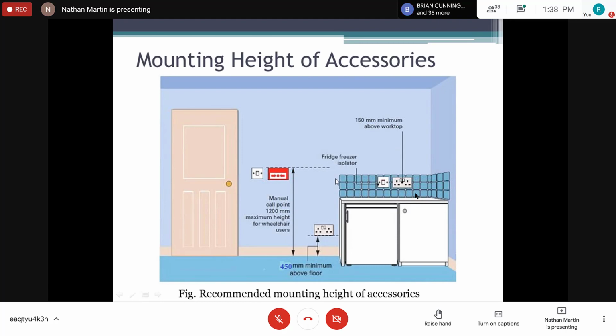All right, so this is basically just typical mounting heights. However, we're talking about from the finished floor. So if you are doing a new installation, guys, you need to make allowance for your tiles. But what if they never put in the flooring before and you need to position your boxes? The diagram will indicate the measurement from the finished floor to the ceiling. This is why the diagram is an elevation plan. It will show you what this distance should be, whether it be 9 feet or 10 feet, and hence you can measure from where your ceiling is going to be to your outlets or your accessories.